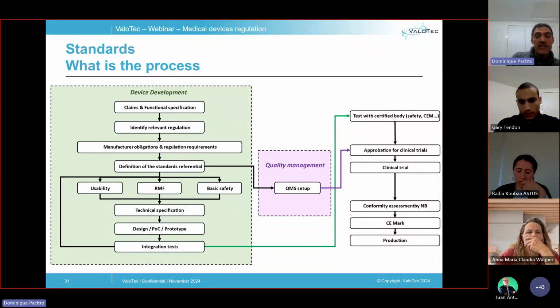Then, as usability is a cornerstone of medical device development, it should start early in the project to get the definition of the user interface. In parallel, a risk analysis is also mandatory, whatever the device class, and should start soon to identify the risk control means. A first iteration on basic safety standards is useful to get the main requirements, for example electrical insulation in terms of leakage currents or accessible parts' maximum temperature.